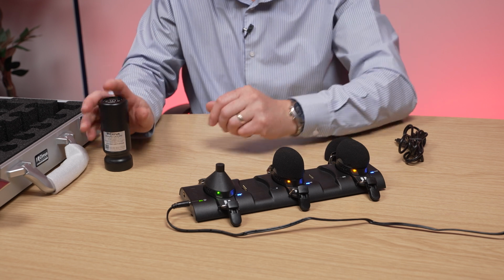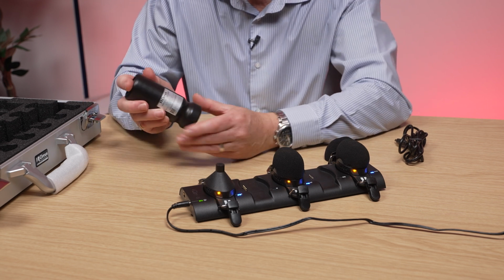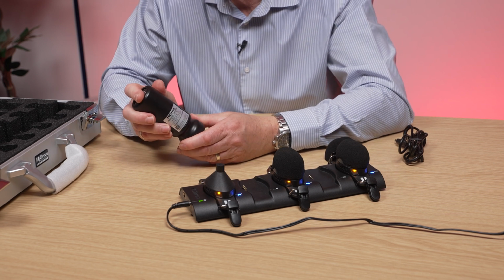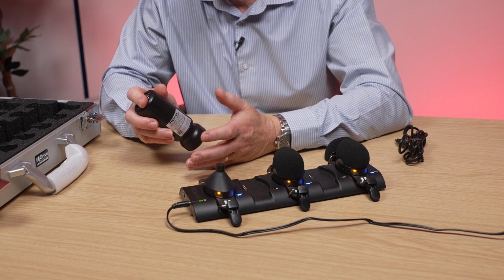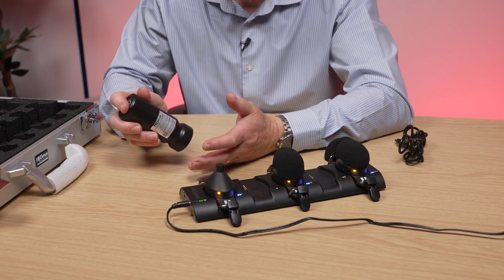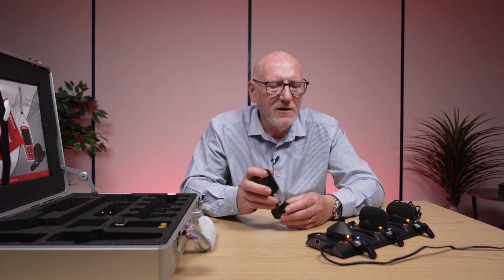Let's have a look at calibration of these. So, as I said before, if you take the windshield off, we have the microphone. We're using a standard calibrator that comes with the kit. Usually it calibrates at 114 decibels. You can also use other calibrators to calibrate it at 94 decibels, whichever one that you've got to hand.